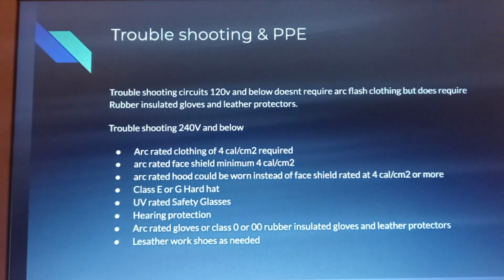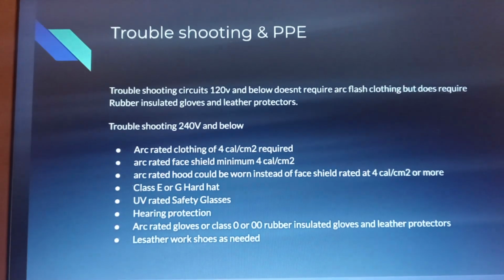So troubleshooting circuits of 120 volts and below doesn't require arc flash clothing, but does require rubber insulated gloves and leather protection when necessary. And troubleshooting 240 volts and less is arc rated clothing of 4 cal/cm². Also a face shield of the same requirements or rated hood of the same requirements. And you need a class E or G hard hat, UV rated safety glasses, hearing protection, arc rated gloves, or class 0 or class 00 rubber insulated gloves and leather protectors. Leather work shoes are also needed.